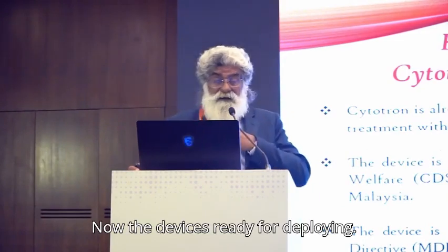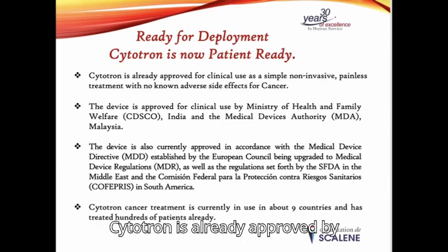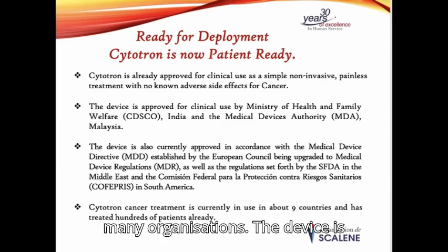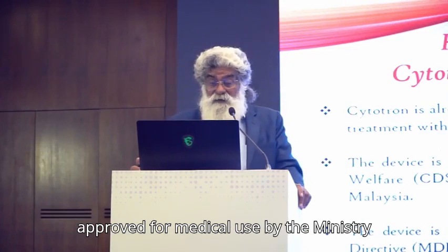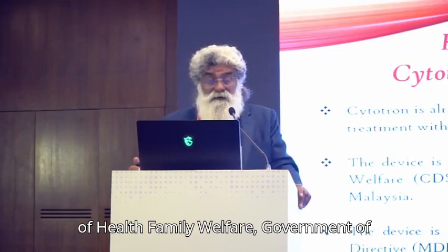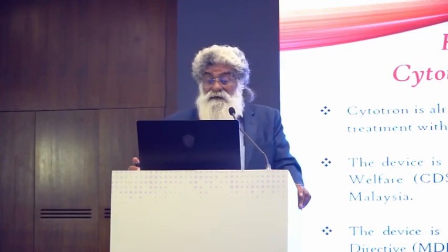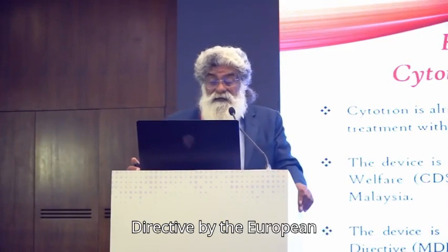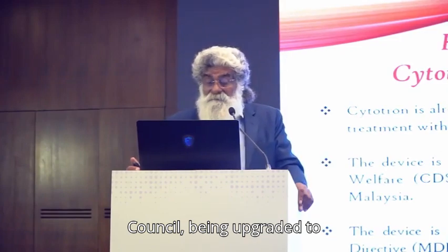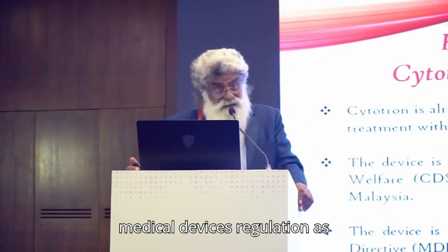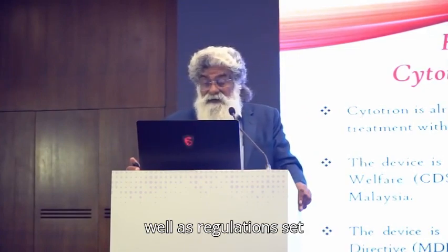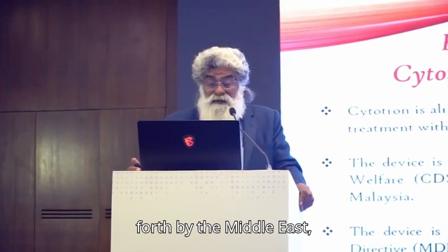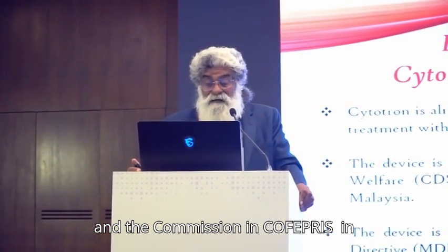Now that the device is ready for deployment — Cytotron is already approved by many organizations. Cytotron is approved for clinical use by the Ministry of Health and Family Welfare, Government of India, and Medical Devices Authority, Malaysia. The device is also currently approved in accordance with the Medical Devices Directive by the European Council, being upgraded to Medical Devices Regulation, as well as regulations set forth by the Middle East Saudi Food and Drug Administration and commissions in South America.